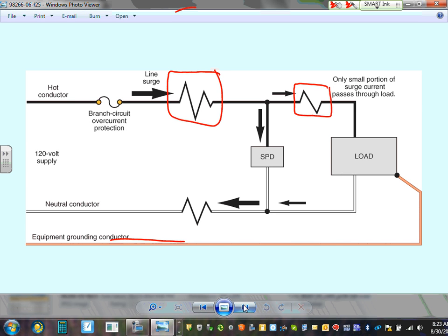Thank God these do not happen often, guys. Lightning, surges, it's not normal. These are abnormal operation. They call them transients because they don't stay. If they stay, they damage your equipment, no question. They're short, ugly, bad, and infrequent. So the surge protective devices sense them, shunt them down, and take them to the ground. After it goes, your laptop will survive that transient situation. It could be caused by lightning, transmission lines, switching, or internal switching inside your building.